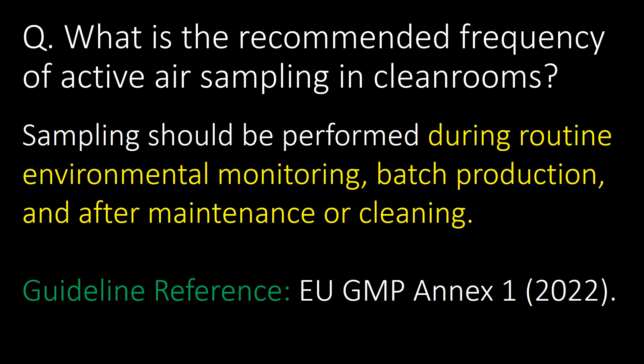What is the recommended frequency of active air sampling in clean rooms? Sampling should be performed during routine environmental monitoring, batch production, and after maintenance or cleaning. Guideline reference: GMP Annex 1.